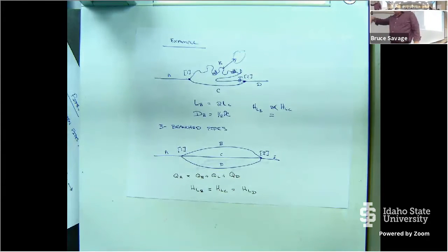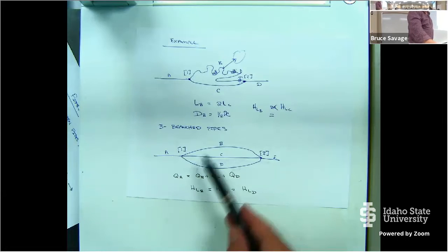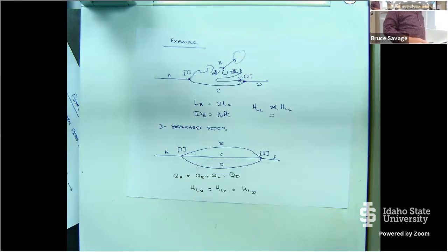This is like our walking around the block concept, but now we're going to cut through the block. But we still end up from point 1 to point 2, we still have the same delta Z across those two. So it doesn't matter how many branches we have, or how much head loss each branch has. If it has flow going through it, the system is going to balance, and the head loss across those individual branches is going to be the same. Okay. And it's going to compensate by adjusting the flow rate.